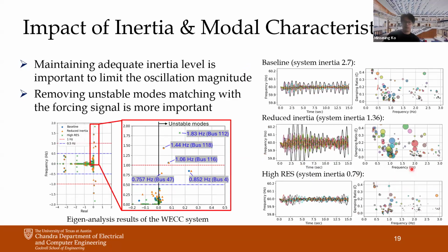And another highlight of our research is the impact of the inertia and modal characteristics. I'd like to start from these right figures. In the baseline case, the WECC system has a systemic inertia of 2.7. When we implemented the data center in this baseline case, the maximum peak-to-peak magnitude of the oscillation was around 0.2 Hertz. If you reduce the inertia constant of the synchronous generators within the WECC system, and the systemic inertia becomes 1.36, we can see a larger amplification of the oscillation magnitude compared to the baseline case.